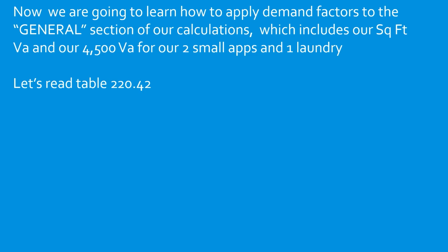All right, y'all, now we're going to learn how to apply the demand factors to the general section of our calculation, which includes our square foot VAs and the 4,500 VAs for our two small appliance and one laundry circuits. So let's head over to table 220.42. It's going to be on page 72 of the 2017, and it's going to be on page 76 of the 2020. Pause the video now, and you can pick back up when you get there.